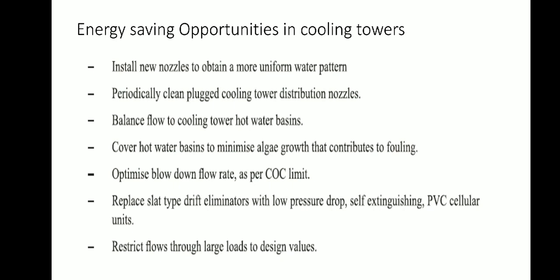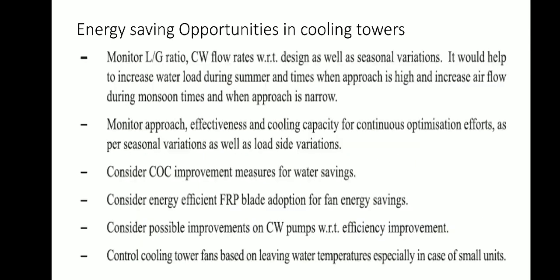Periodically clean plugged cooling tower distribution nozzles. Balance flow to cooling tower hot water basins. Cover hot water basins to minimize algae growth that contributes to fouling. Optimize blowdown flow rate as per COC limit. Replace slat type drift eliminators with low pressure drop self-extinguishing PVC cellular units. Restrict flow through large loads to design values.